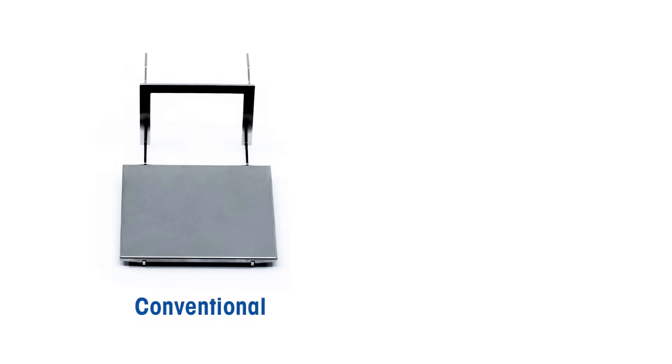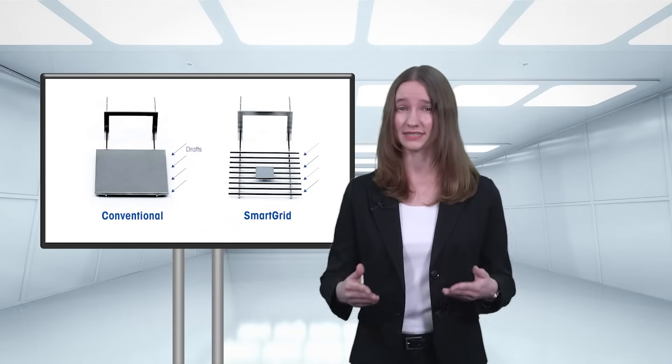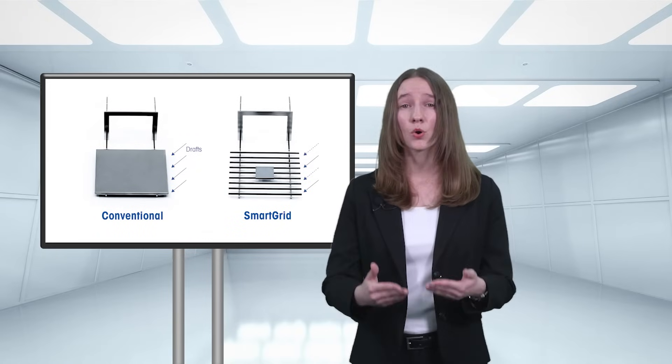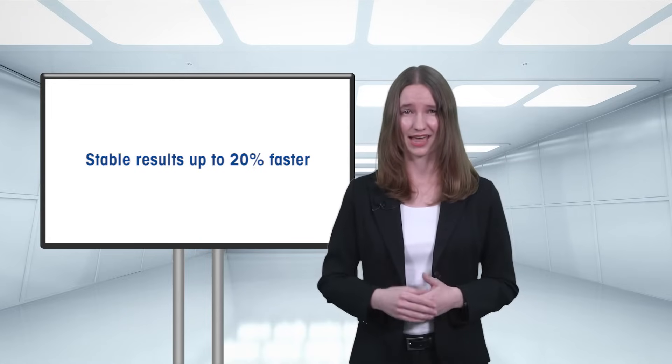Compared to conventional weighing pans, the grid structure has less surface for destabilizing air turbulence to act on. With this technology, you will get more stable results up to 20% faster, boosting productivity in your lab.